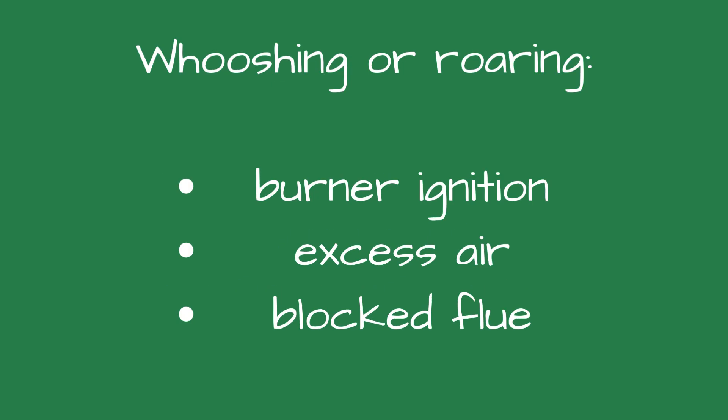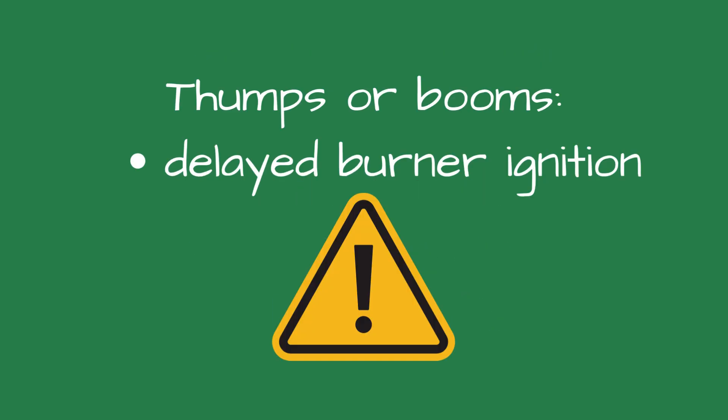Number ten is whooshing or roaring. This could be caused by improper burner ignition, excess air in the combustion, or a partially blocked flue. Number eleven, loud thumps or booms could be caused by delayed ignition of fuel inside the combustion chamber. Delayed ignition is dangerous — repeated hard starts stress and can crack refractory and increase explosion risk.